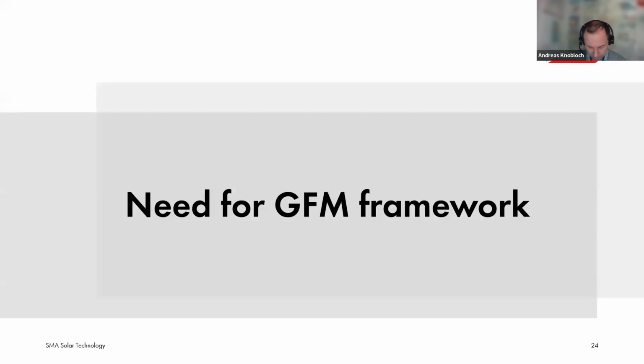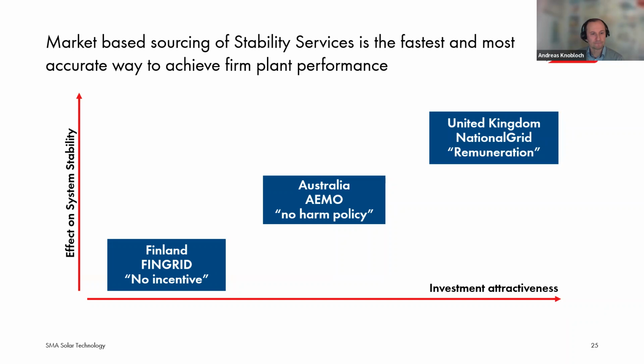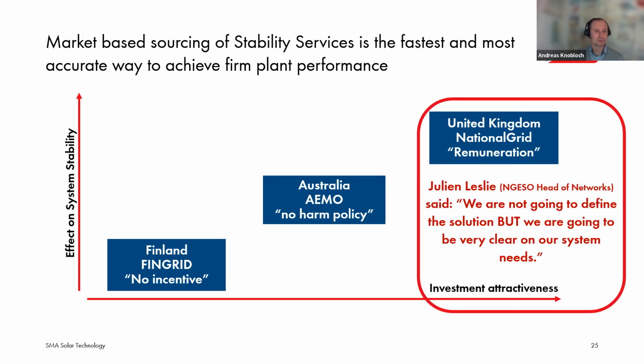Okay, I will come to my last chapter. And this is the need for a grid forming framework that we see. So now, if you look at the thoughts regarding grid forming requirements and provision and so on, we see there are different approaches. One approach, for example for some parts of the Finnish grid, is: for grid forming services, we would not like to give any incentives or compensation. Power plants should provide it on their own. It should be mandatory. Then there are some approaches in Australia, where there is the no harm policy. That means, if you want to connect a new power system to the power grid, you need to show that you do not harm. And if you harm, then you need to pay the costs, or somehow improve it, so that you do not harm the system.